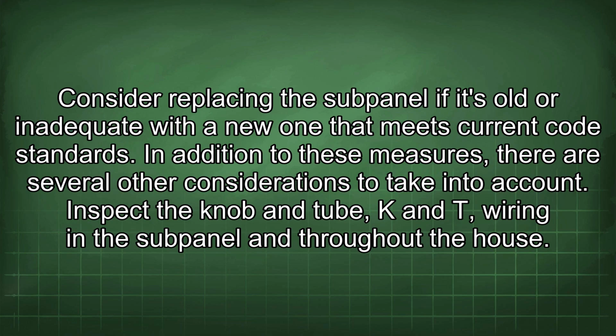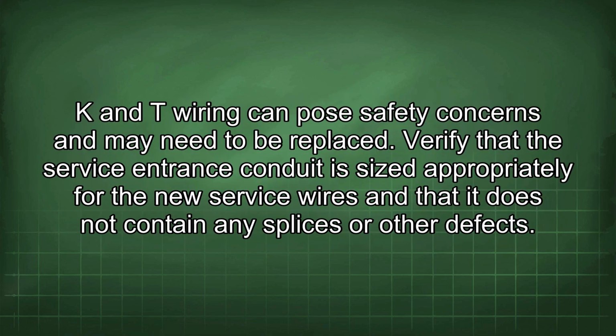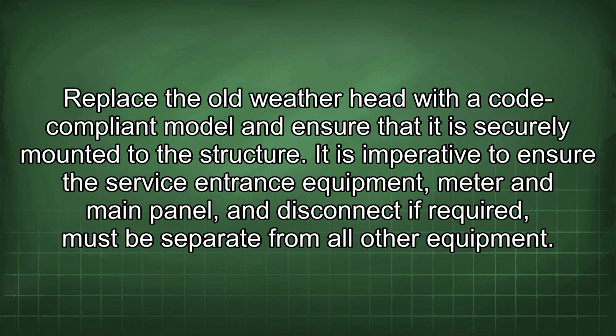Inspect the knob and tube, K and T, wiring in the subpanel and throughout the house. K and T wiring can pose safety concerns and may need to be replaced. Verify that the service entrance conduit is sized appropriately for the new service wires and that it does not contain any splices or other defect. Replace the old weatherhead with a code-compliant model and ensure that it is securely mounted to the structure.